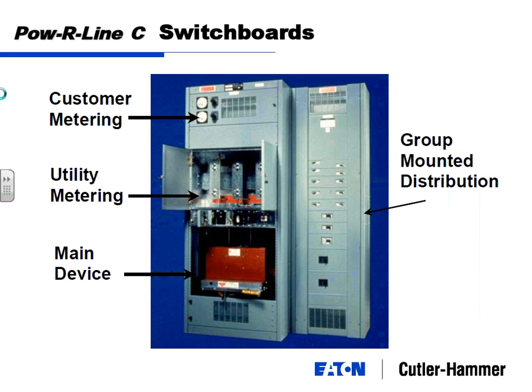And the way it physically looks is this will be your main structure. So you can have some metering at the top, and these, of course, are the old analog meters, which nobody uses; everybody uses digital meters now. Utility metering compartment stuck in the middle, where the utility can come in and put in their CTs. A main device here, which then feeds the horizontal bus that would run behind this distribution section. So there would be a vertical bus tied into the horizontal bus that feeds all these breakers. Notice they're different depths. So this one, because it's got a big breaker, may need to be 30 inches deep. This one, because it's only got smaller breakers, maybe only needs to be 18 inches deep. It's common practice to front and rear line them. It's not mandatory, but it's got a little more aesthetic appeal, I guess.